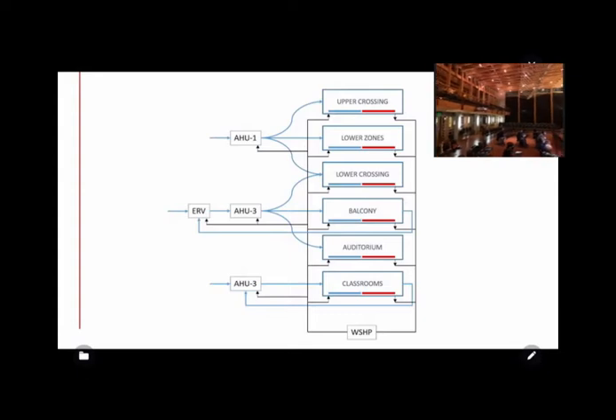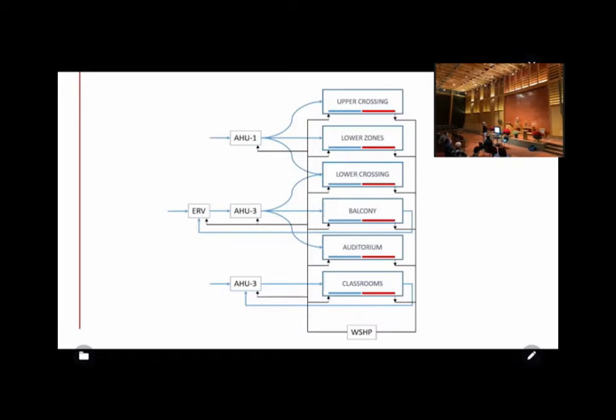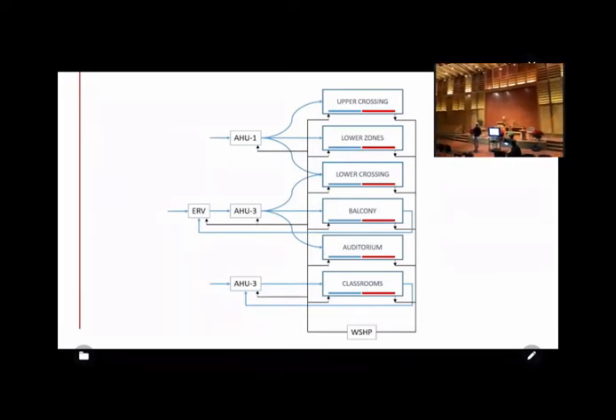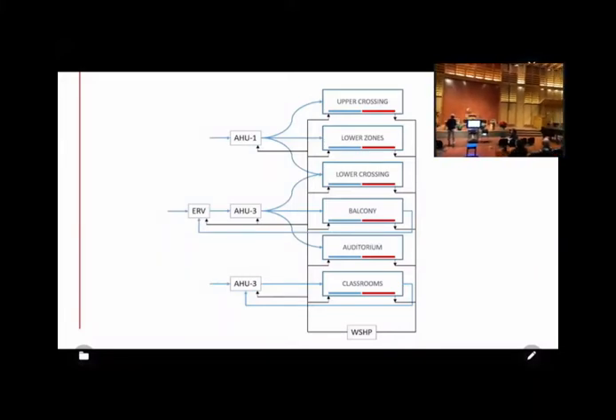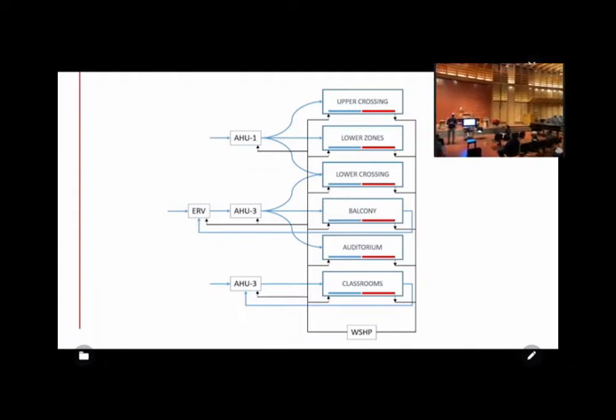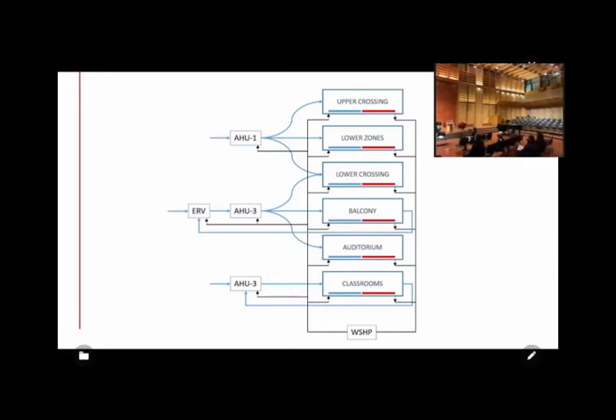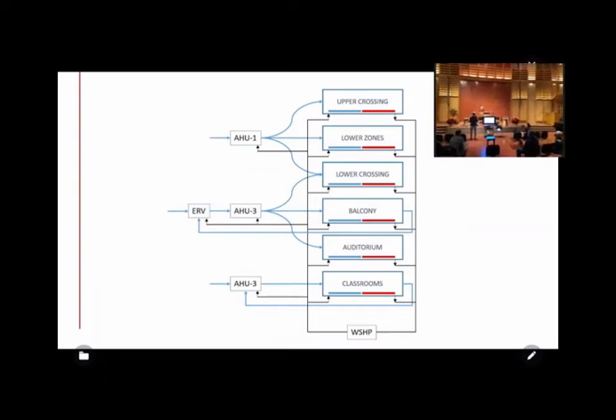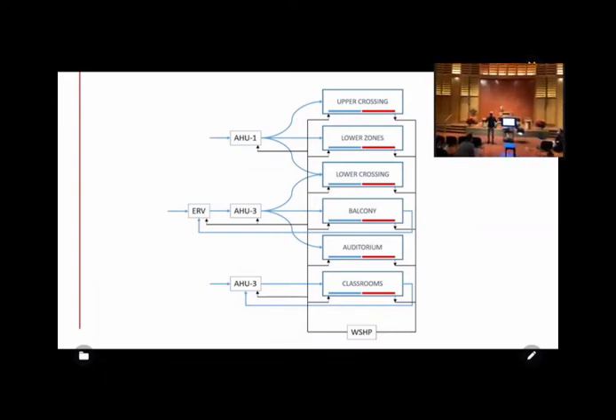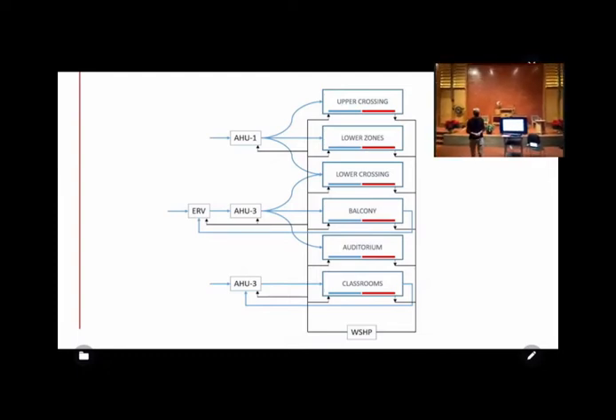And a concern we did not have, which hopefully will lead into something that Mike and Tom are going to talk about, was condensation. It proved out to be a concern that we should have had, that the radiantly cooled floors were going to cause condensation problems. This was a concern we had had on the Aldo Leopold building, because that building was supposed to be really heavily naturally ventilated. And we were worried that if you switch over from natural ventilation to mechanical cooling, you're going to get a building full of moist air with a cold floor, and you're going to have a thunderstorm in your lobby or something.